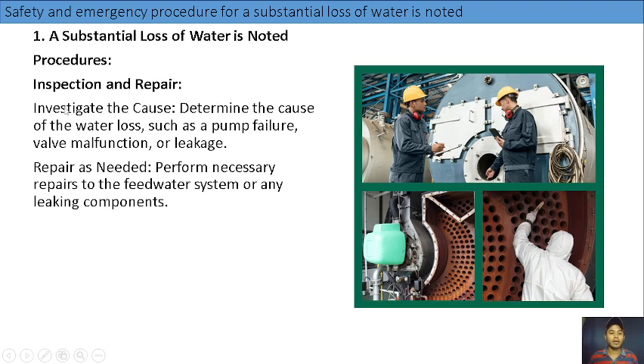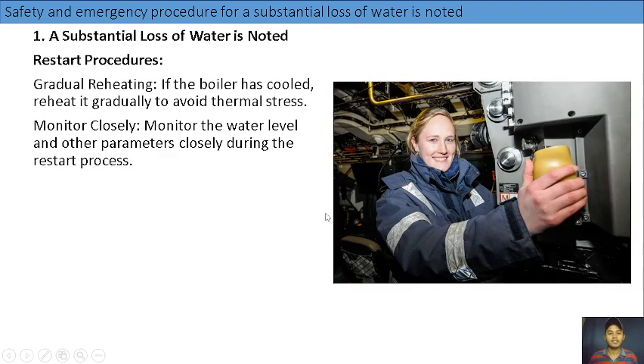Then, for inspection and repair, investigate and determine the cause of the water loss, such as a pump failure, so check the pump. Valve malfunction, maybe the valve is closed or not opening, that's why there is no flow. Or leakage, so you should check the tubes and pipes for leakage, and then repair as needed. Perform necessary repairs to the feed water system or any leaking components. Next, if everything is now okay, you can restart your boiler. Gradual reheating: if the boiler has cooled, reheat it gradually to avoid thermal stress, and closely monitor the water level and other parameters during the restart process. If everything's okay, then you're good now. Okay.